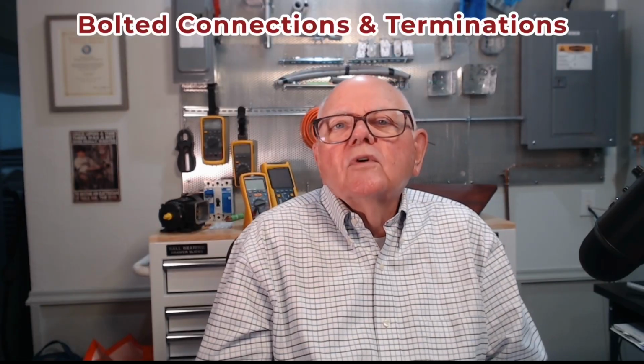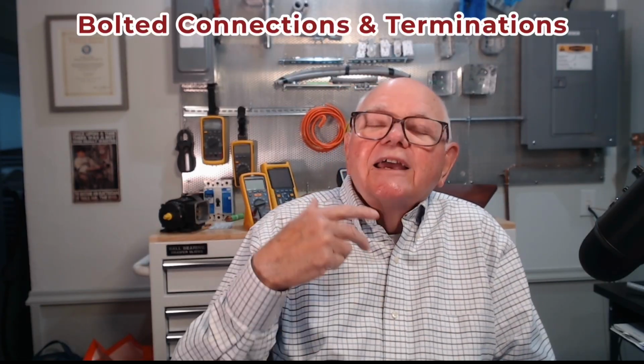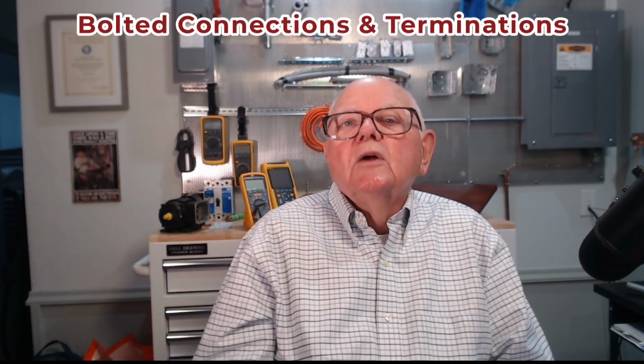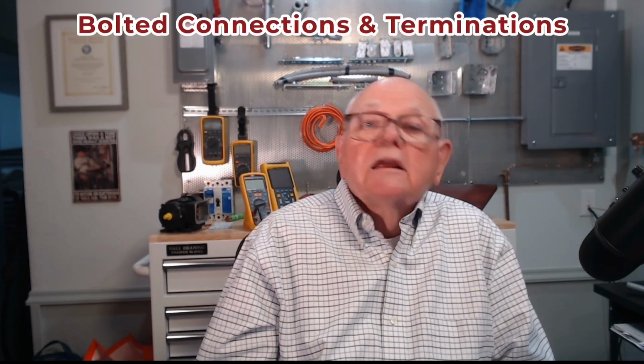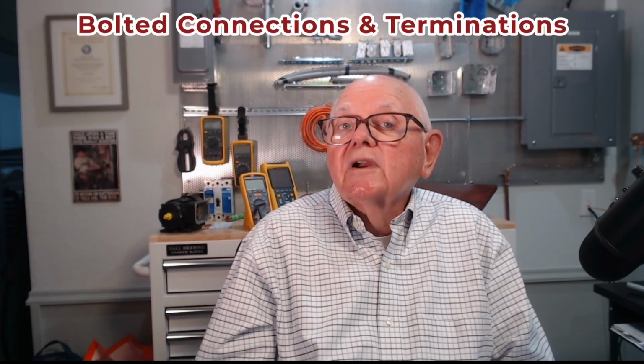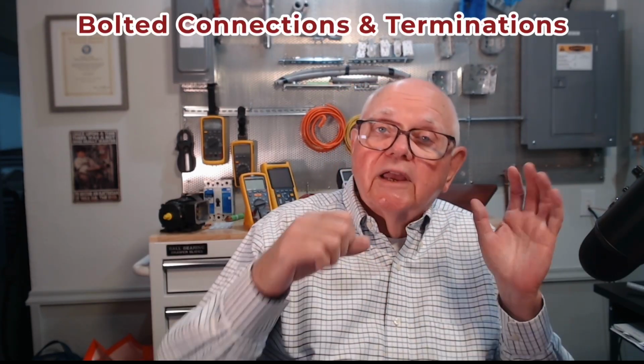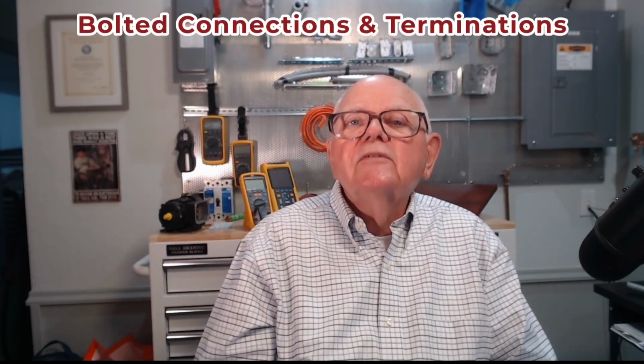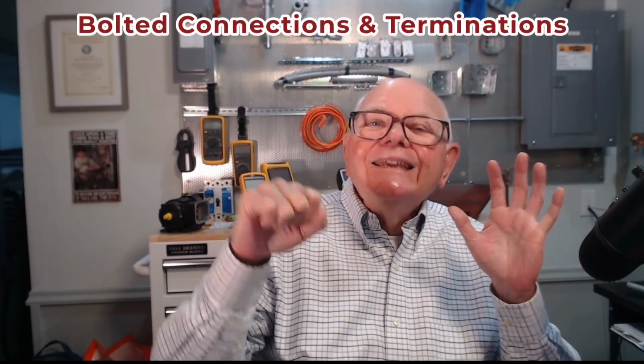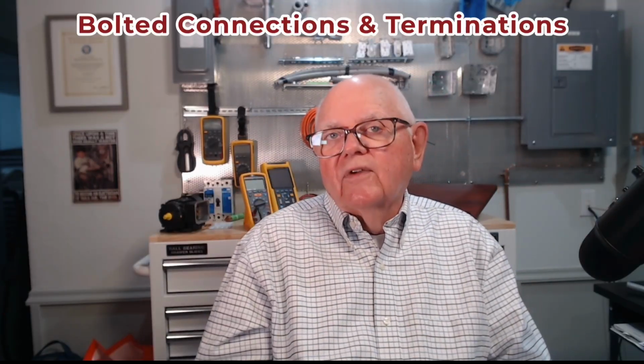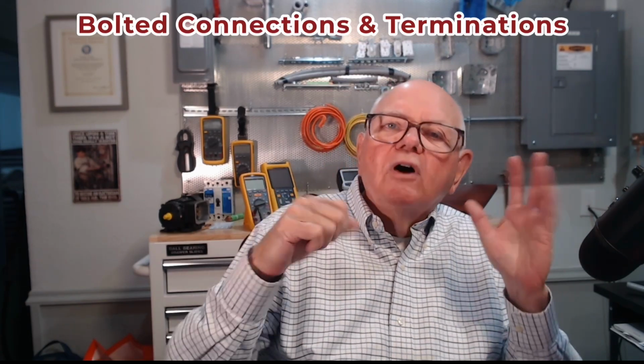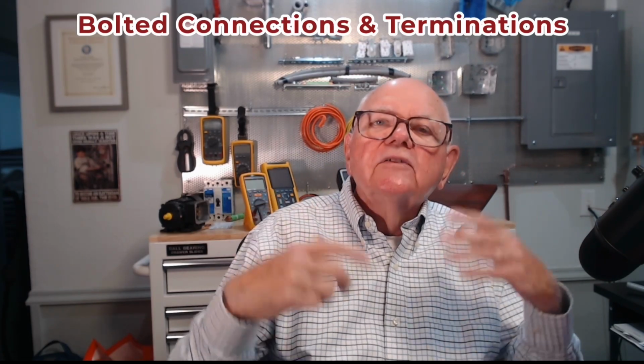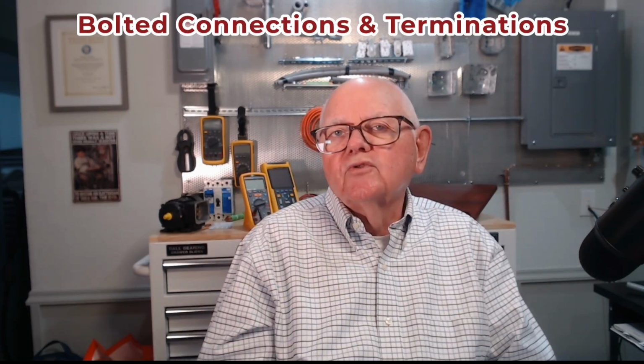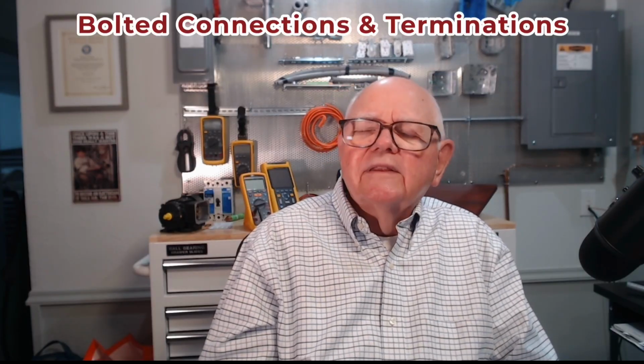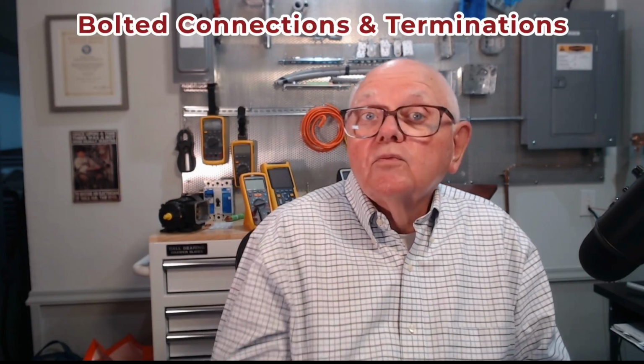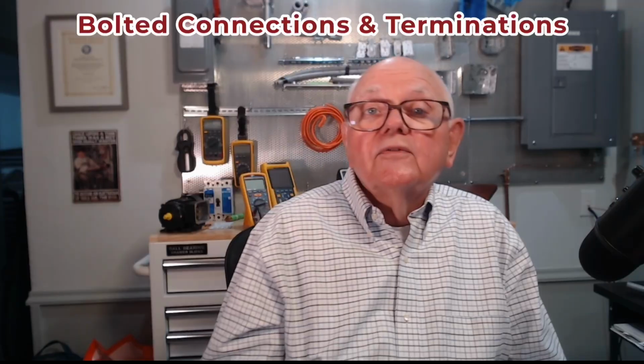So 110.14 says, NFPA 70B says, when I go back to do maintenance on that, one way to check that torque connection, say on those bolts, would be to go ahead and get a torque wrench out and torque it down to what? 90% of that original torque value. Don't torque it back down to 100% when you're doing the maintenance. It tells us 90% of that original torque value. So that's one way that I can do it. Another good way would be infrared thermography, right?